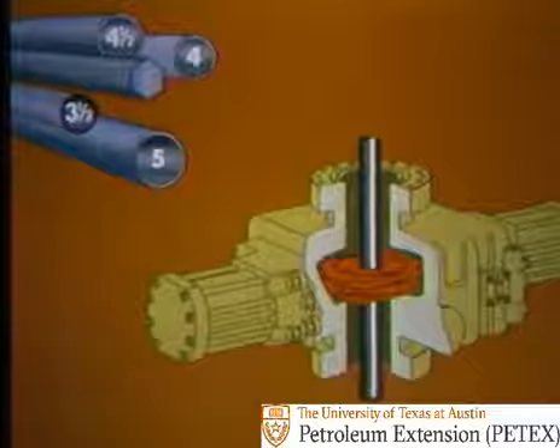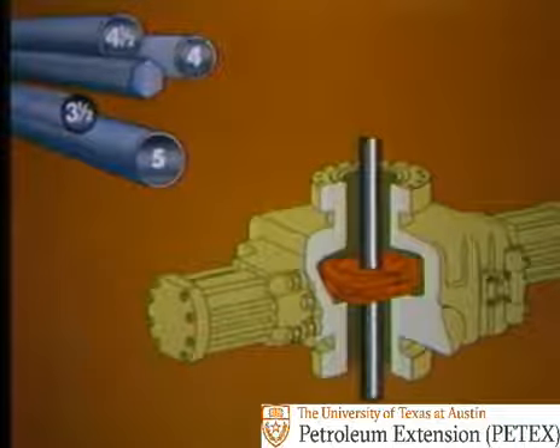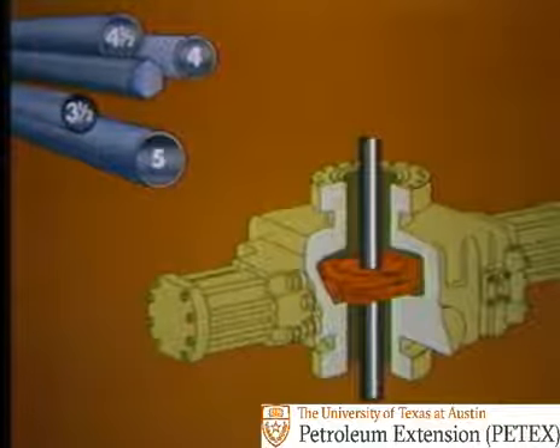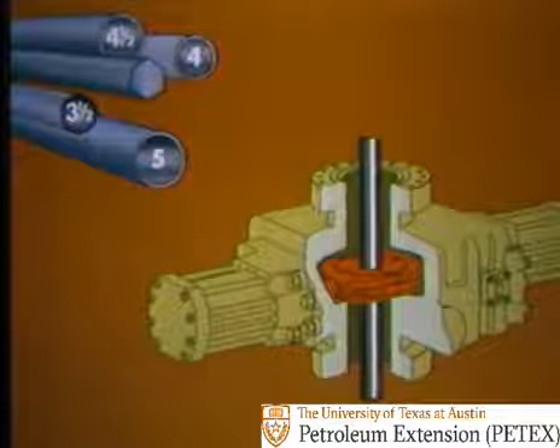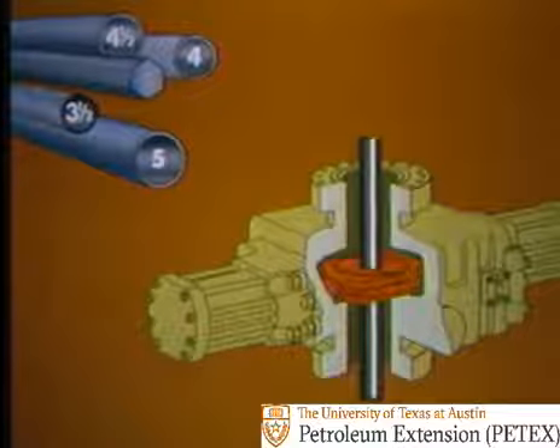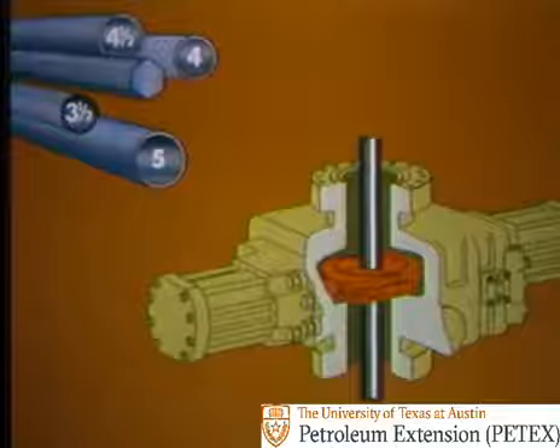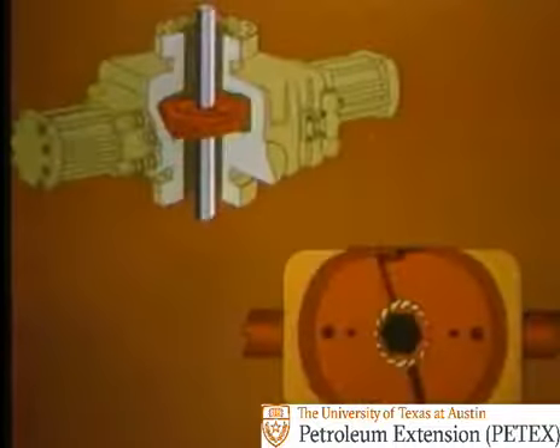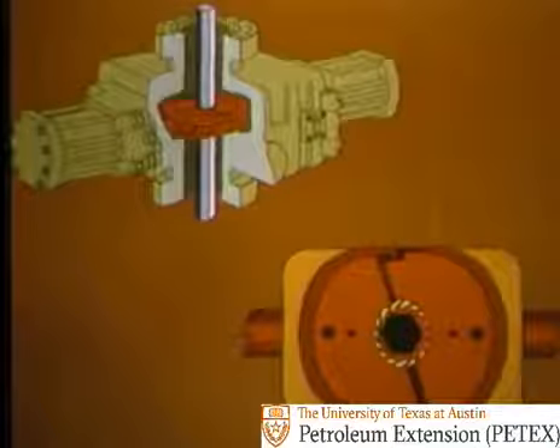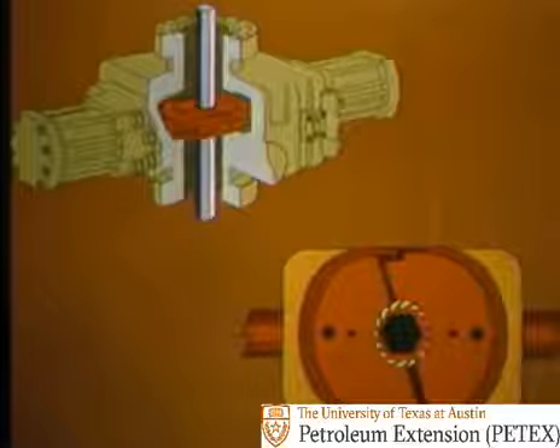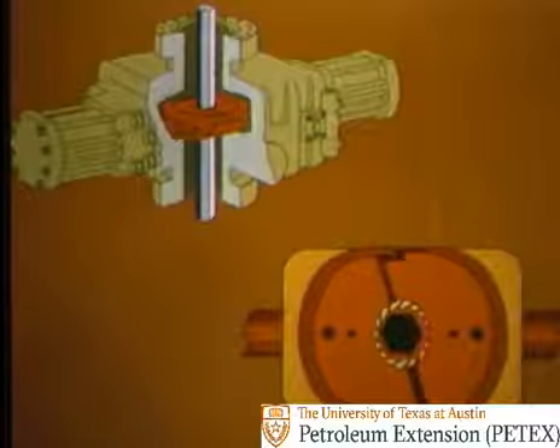However, variable bore rams are available. They can close on a variety of pipe sizes, like on 3.5-inch pipe, 5-inch pipe, or any size in between. Also, they can close on hexagonal Kellys, and in some cases even on square ones.